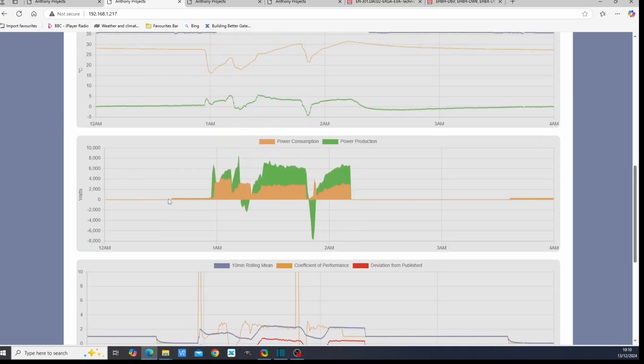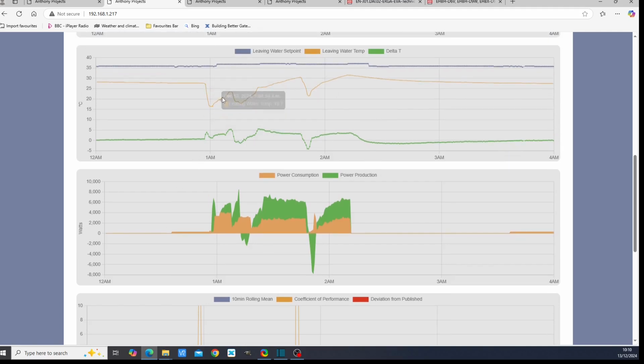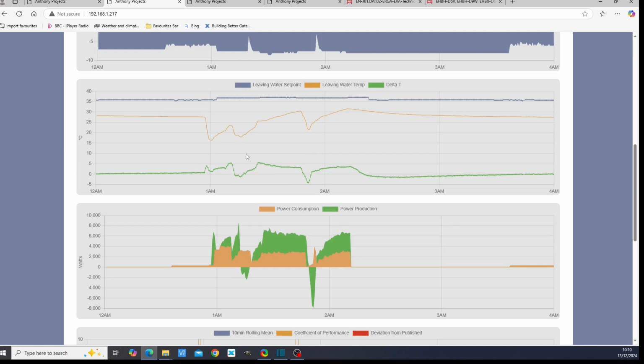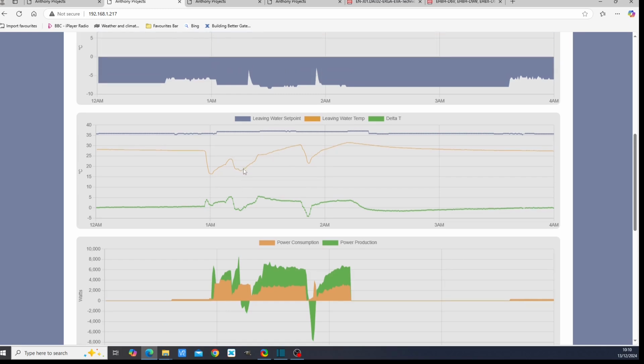So as you can see, leaving water temperature here, it rises and then it falls and then it rises again. And you can see it's kind of dropped the ball. The produced heat from the compressor just sort of switches off. So as you can see, the temperature falls and then it decides to put the backup heater on again. And it does a bit of a fumbling job of getting the leaving water temperature up. But eventually it settles above 20 degrees Celsius and then it's just the compressor. As you can see, the compressor output is about 2.7 kilowatts here. It's not 100%. But it is enough to bring the leaving water temperature up to 30 degrees before we get a defrost cycle.